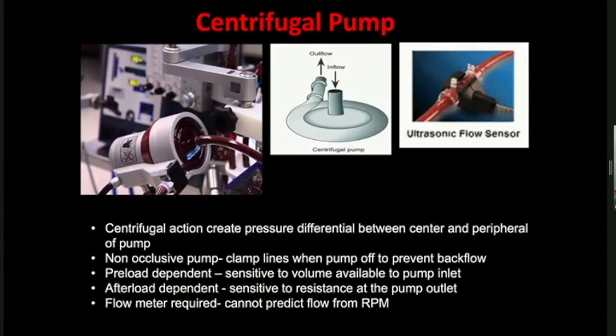The ECMO circuit uses a centrifugal pump. It's termed centrifugal because the motor spins in a centrifugal fashion, creating a gradient between the inflow and outflow. This pressure gradient creates the ability for blood to be sucked out of the body and pumped back to the patient. Unlike the roller pump in CKRT circuits, this is a non-occlusive pump, which means that when the pump suddenly stops, blood will actually flow backwards. When changing the pump or circuit, you need to clamp the lines to prevent this blood backflow.